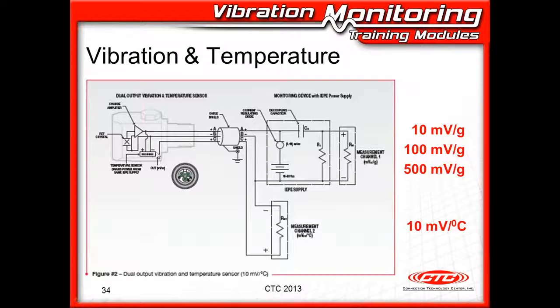Also, we have a small integrated circuit inside this accelerometer that measures the temperature, 10 millivolts per degree C. And this is simply a DC voltage output. So you have to have the power turned on to the vibration side of the sensor so that you can measure the DC temperature on pins C and B. So simply 10 millivolts per degree C DC. Vibration-wise, these sensors are available at 10 millivolts per G, 100 millivolts per G, and 500 millivolts per G.